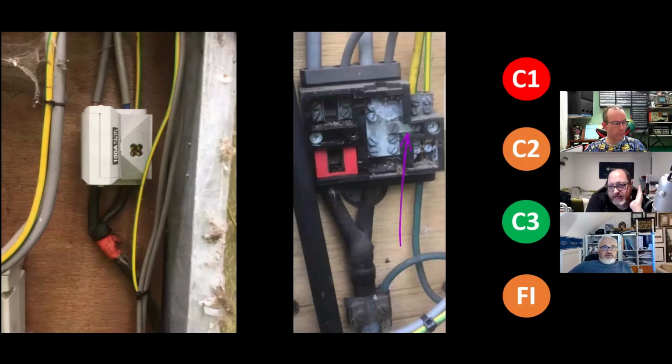Let's say that I've got the cover on and the link is out. I can do a continuity test between the neutral incomer, isolated, and the earth. If I have continuity, then I have my PME. If I don't, then I have TNS. So just an extra step. That would be an FI in that case. Oh, Dave, that could be in a webinar called "The Hidden Test" that BS 7671 doesn't tell us to do.